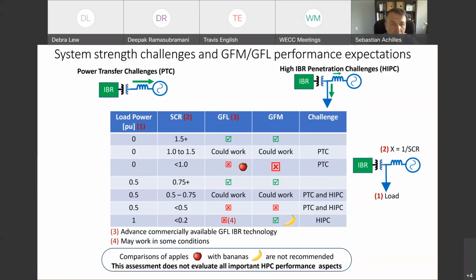The first 3 rows have the load equal to 0, meaning we don't consume any load. And this is the same as the power transfer problem that we were discussing before, and that is mentioned in the upper left. If the short circuit ratio, say, is higher than 1.5, using the numbers that Julia was describing, we can argue about whether it's 1.5 or 2 or a number around that, but in principle, for high short circuit ratios, it is expected that grid following and grid forming will have acceptable performance. There is a range of short circuit ratios between 1 and 1.5, for example, I'm postulating, where both of them could work. And this will depend on the details of the control. To say that grid forming works and grid following doesn't work will be an oversimplification, because it depends on what particular inverter and product we are evaluating. But definitely, if the challenge to get that to work or not is related to power transfer.